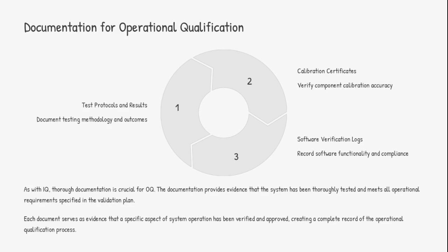Documentation for operational qualification provides evidence that the system has been thoroughly tested and meets all operational requirements. This includes calibration certificates, software verification logs, and test protocols and results, creating a complete record of the qualification process.